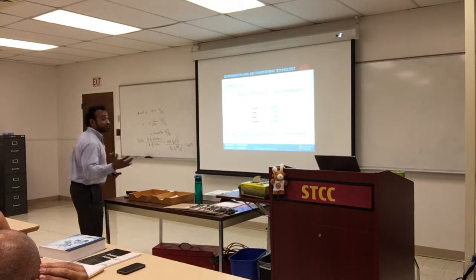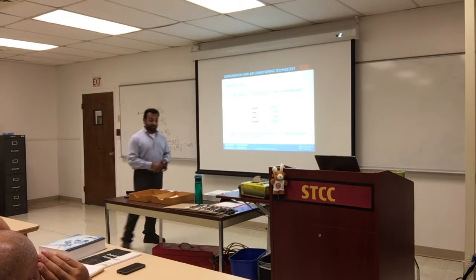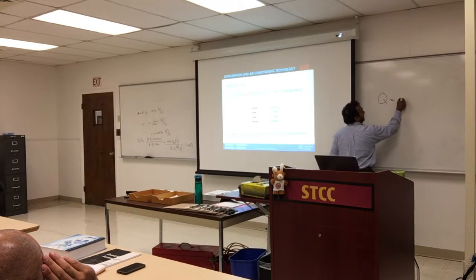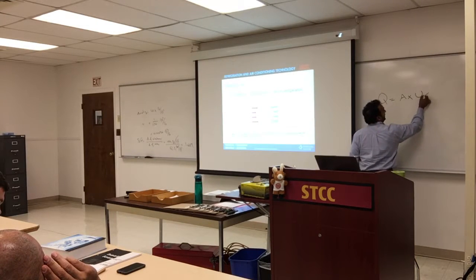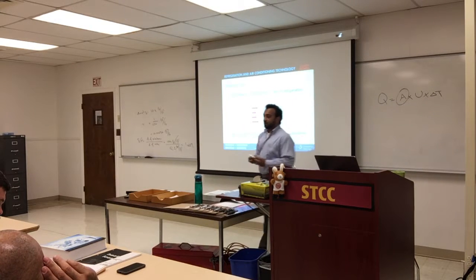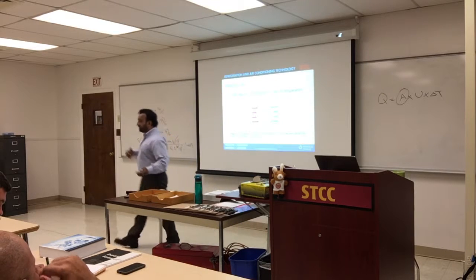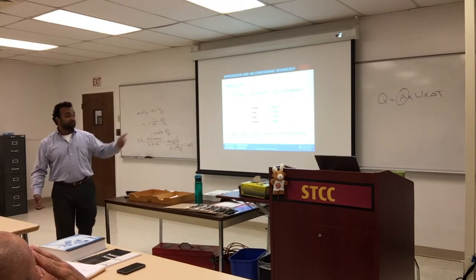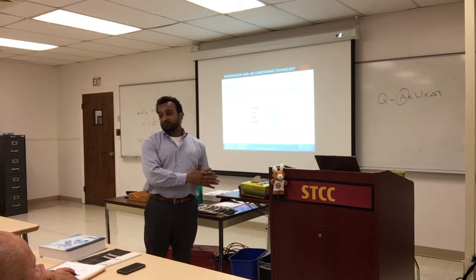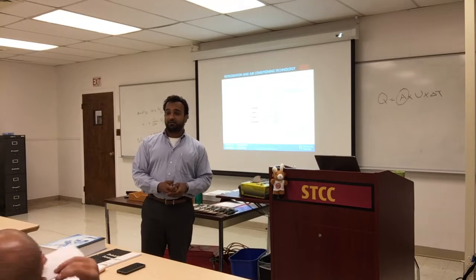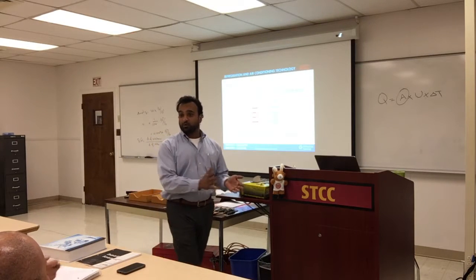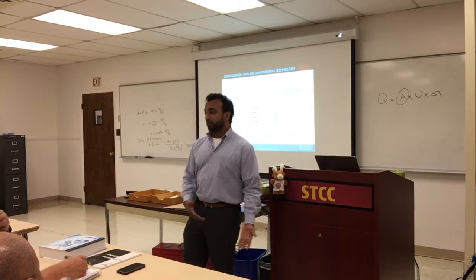And remember that, because that's the basis for all heat transfer. When we talk about heat transfer, we say Q equals area times U times delta T. This is the thing, surface area. So the radiator depends on surface area to have better heat transfer. Baseboards have a lot of fins for more transfer. Your car radiator has more rows, more copper, more fins in it. If you close some of those fins, you're losing surface area, you're losing heat transfer.